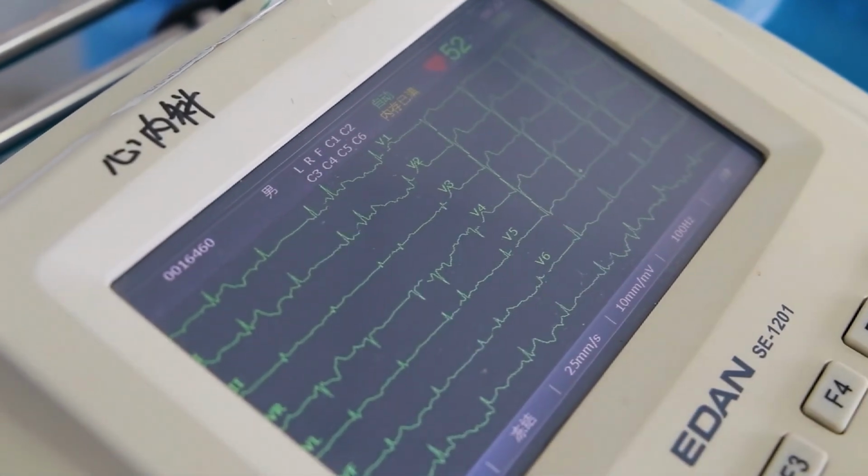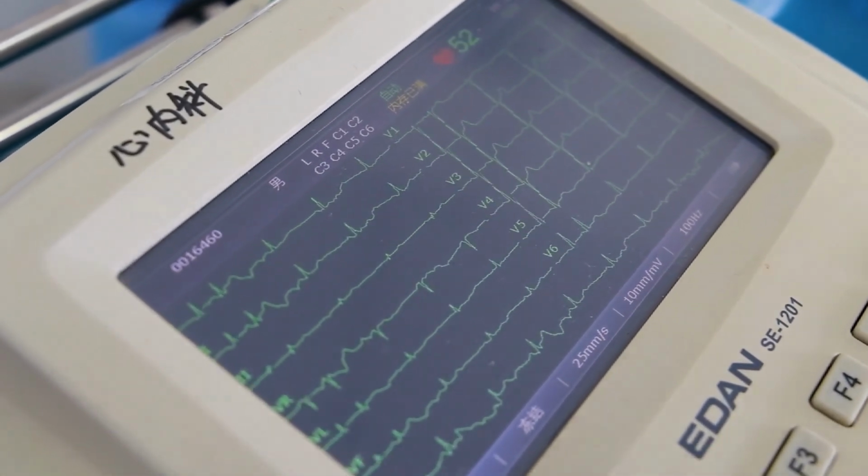So maybe you think of that plus or minus 0.2% as low risk. But if your device is supposed to record 85, and it's giving you 140, then that's no good, right? So at that time you need to do a risk control to get it figured out.